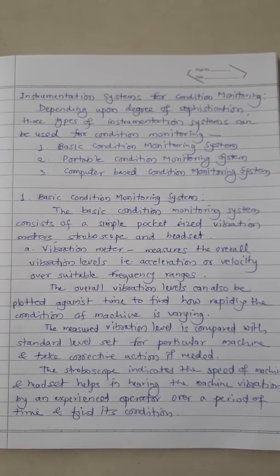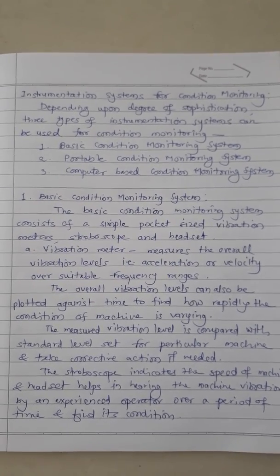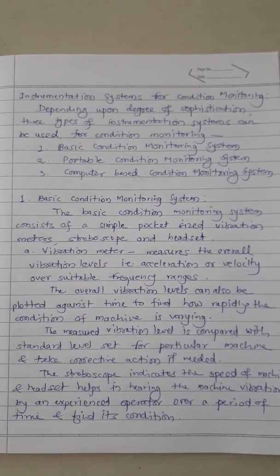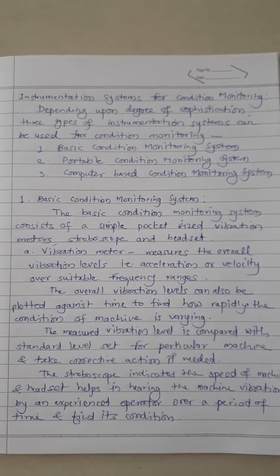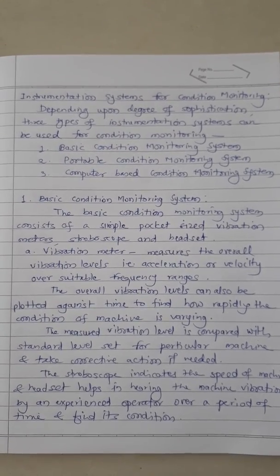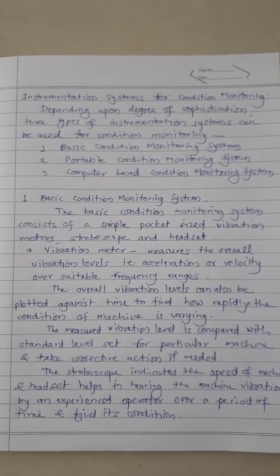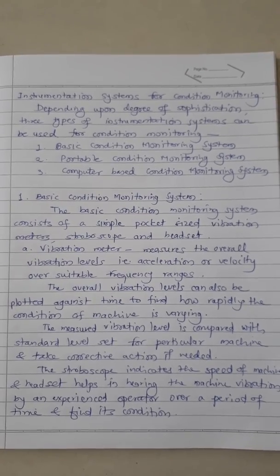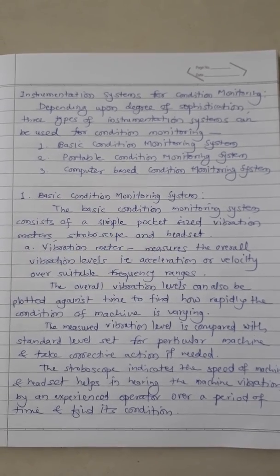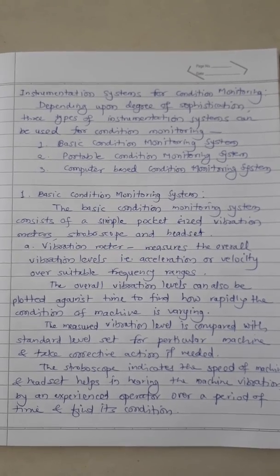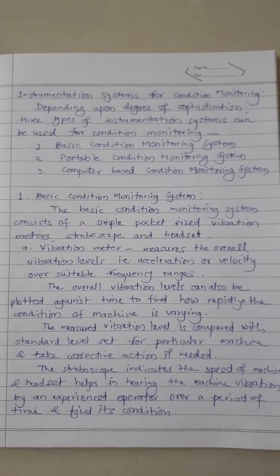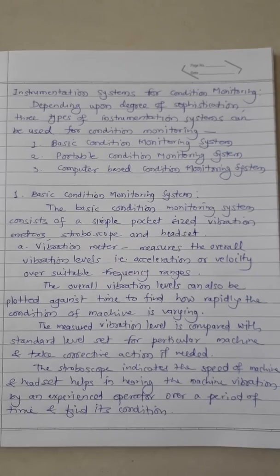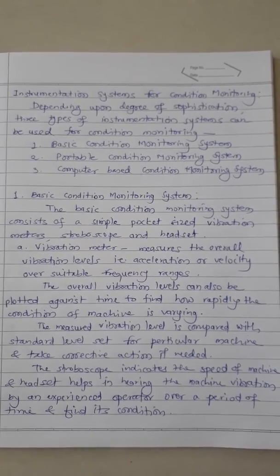The basic condition monitoring system consists of a simple pocket-sized vibration meter, stroboscope, and headset. The vibration meter measures the overall vibration level, i.e., acceleration or velocity over broadband frequency ranges. The overall vibration levels can also be plotted against time to find how rapidly the condition of the machine is varying. The measured vibration level is compared with a standard level set for a particular machine and corrective action is taken if needed. The stroboscope indicates the speed of the machine and the headset helps an experienced operator in hearing the machine vibration over a period of time to find its condition.